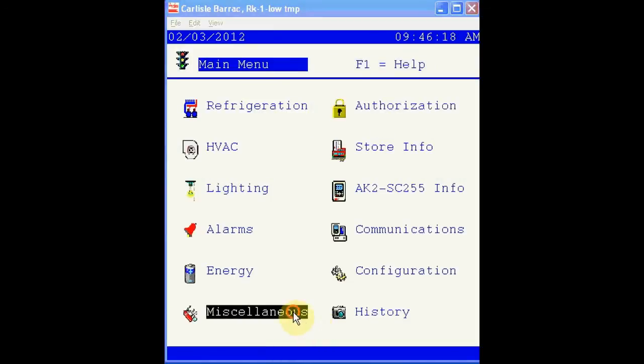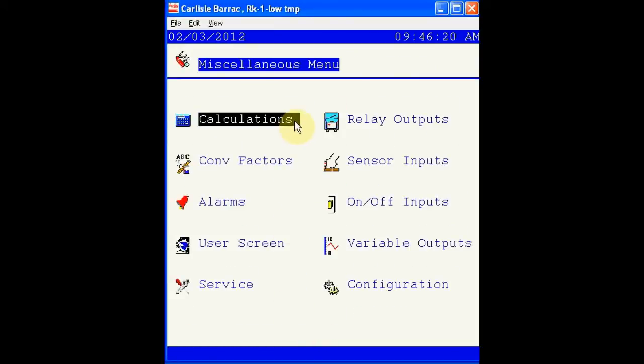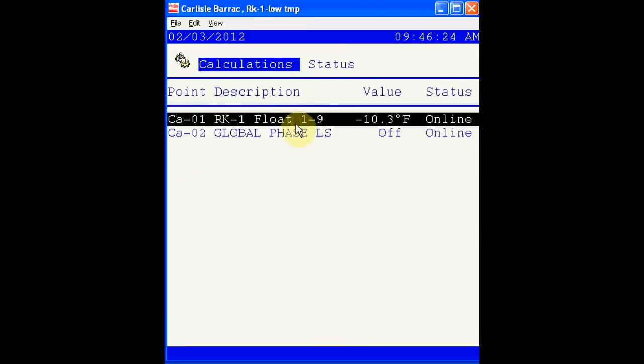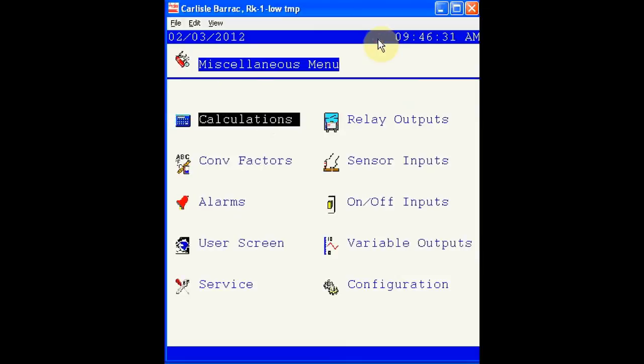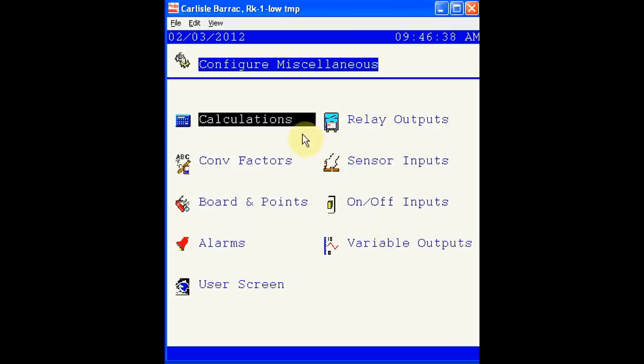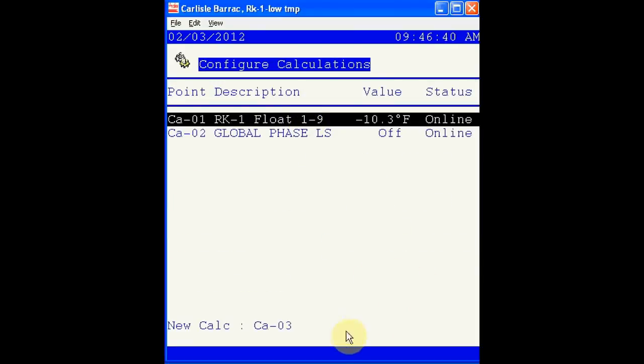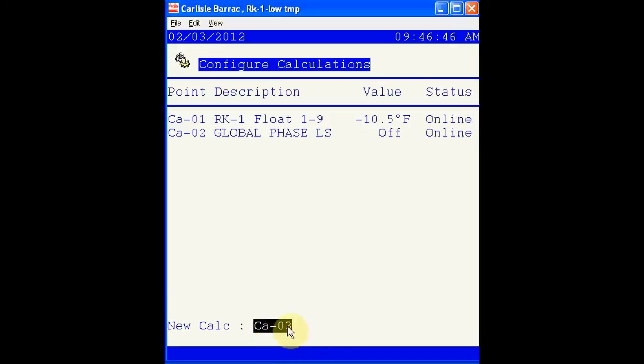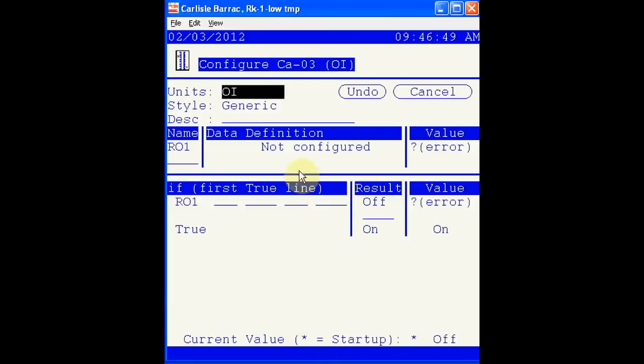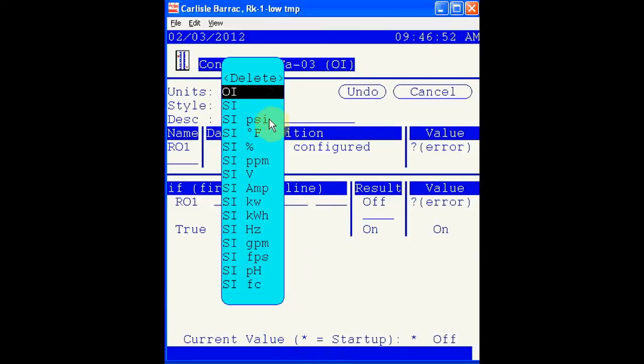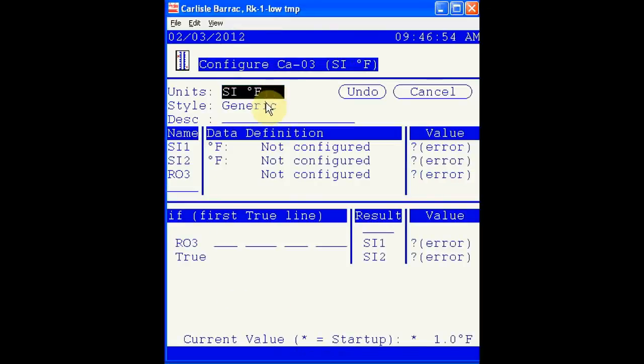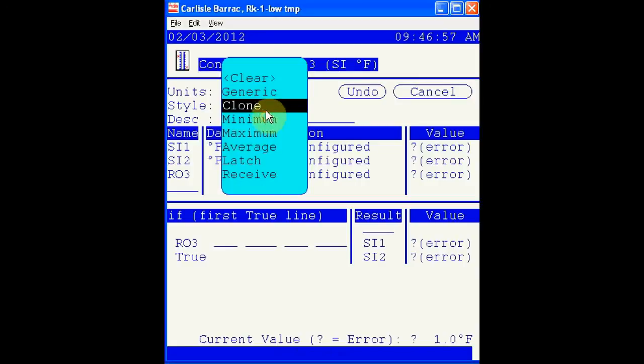Let's say we wanted to create a calculation, in this case the simplest calculation, which would be a sensor clone. Because we're in the status screen, it's not possible to create a calculation here. So, returning to the miscellaneous menu, select Configuration. Next, Calculations. Now you see it's available to create a new calculation, which will be defined as calculation number 3. Let's say we wanted to create a clone, which is the easiest calculation based on the outdoor air temperature.